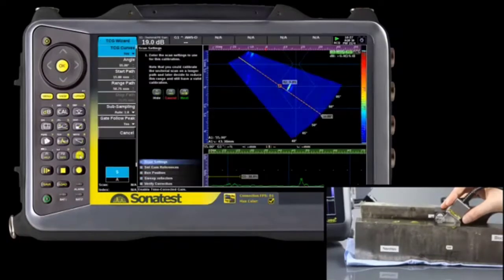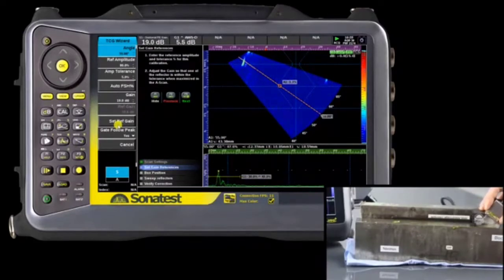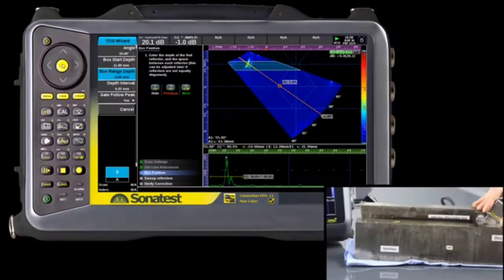Once the type and mode of the curve have been selected, we are entered into the wizard manipulation section. You can change your general inspection parameters in the first step of the TCG wizard. In the next step, you can set your gain reference and curve amplitude reference with the Set Ref Gain and Ref Amplitude button. Make sure to maximise the reflector response before setting it as a reference. The next step is for the extraction box dimensions and desired depth jumps between reflectors. In our case, every reference reflector has a spacing of 6.25 mm.